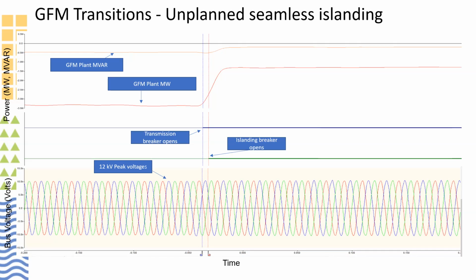This is showing breaker status. We just take the A contact status, bring that in the DFR, everything's timestamped. So this is showing here, this is the transmission breaker opening. This is saying as if there was a fault external of the substation.